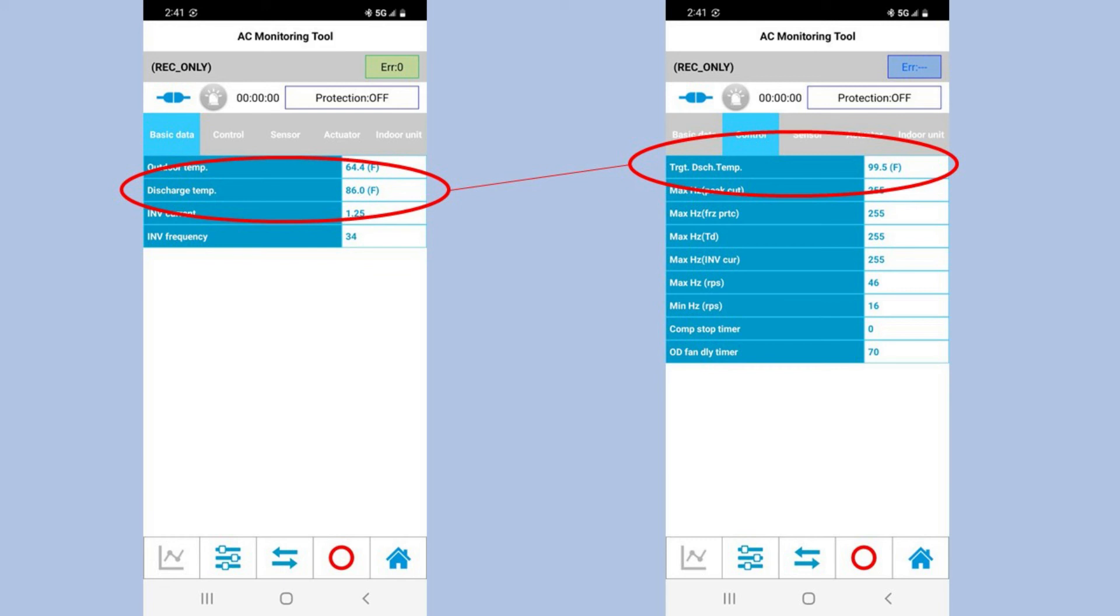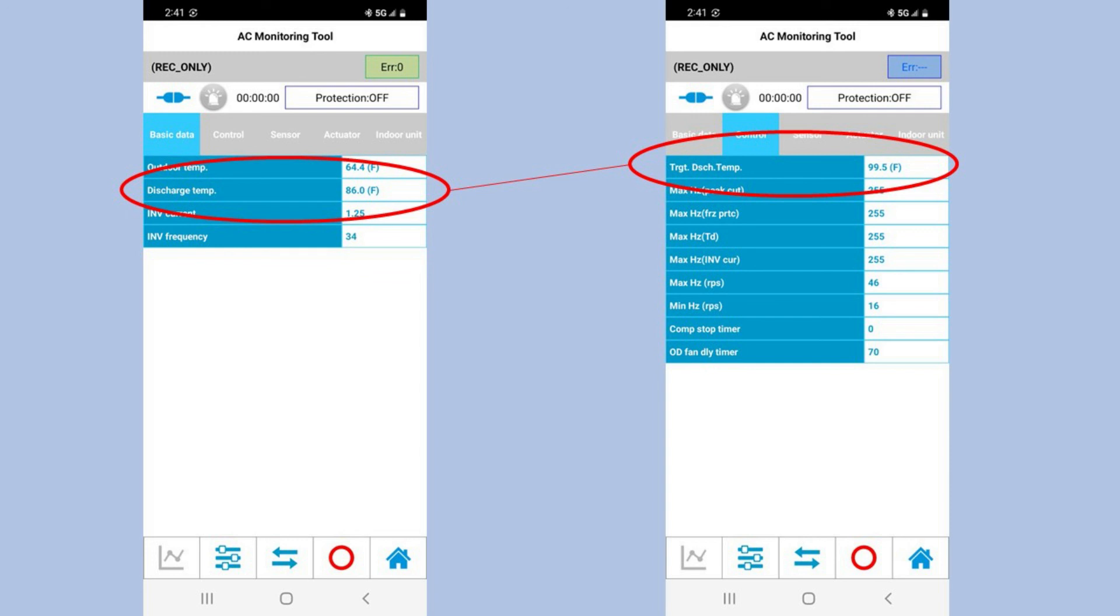The best diagnostic use for this would be to monitor the system after 20 minutes. You can look at the discharge temperature of the compressor and the target, and if it's unable to hit the target, there's a good reason, usually a refrigerant issue. If your gas is way too hot coming back, we're low in refrigerant. If it's way too cold, we have too much. The best way to monitor operation between that and monitoring the indoor head temperature. Again, cooling 42 to 47 on the exchanger and heating 108 to 116. That's considered proper operation. If you're at 42 on the indoor coil and you have really good discharge temperature meeting your target, you just have to get that fan sped up, pushing more heat in that coil if you want it to speed up.